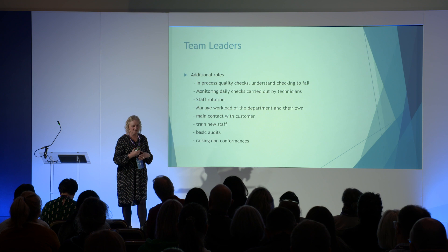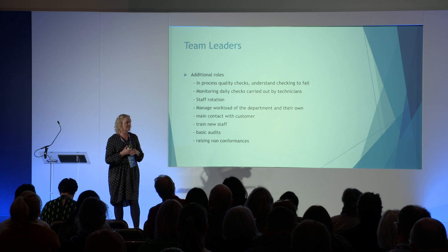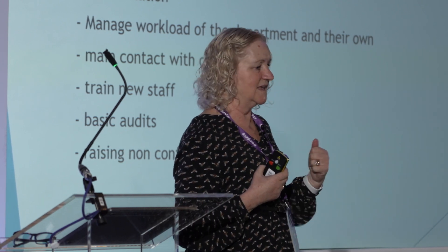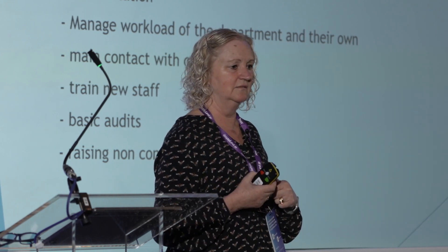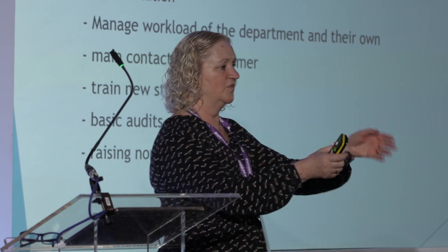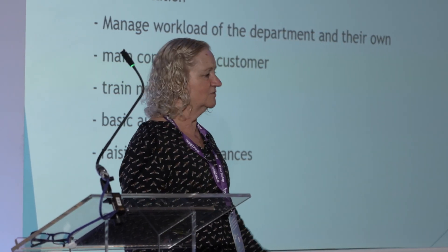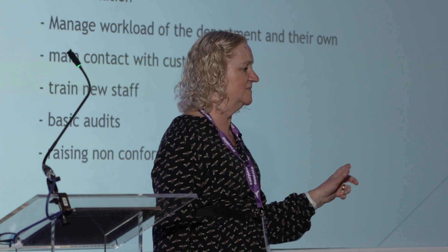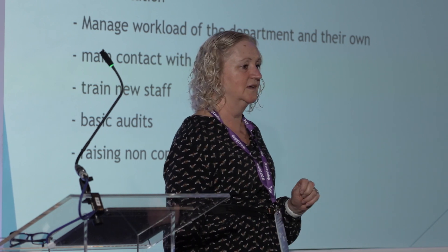What does quality mean to the patient? How many of us have had phone calls from theatre saying, 'I want that set, I phoned 10 minutes ago, where is it?' — 'It's still in the washer.' 'Can you fail the washer and get it to me?' I had a consultant bring a dirty set and say he wanted it in an hour. I asked: do you want it washed or sterilized? The washer takes an hour, the sterilizer takes an hour — if you want it in an hour you've got to miss one out. Realistically it takes four hours. Are we strong enough to have those conversations?